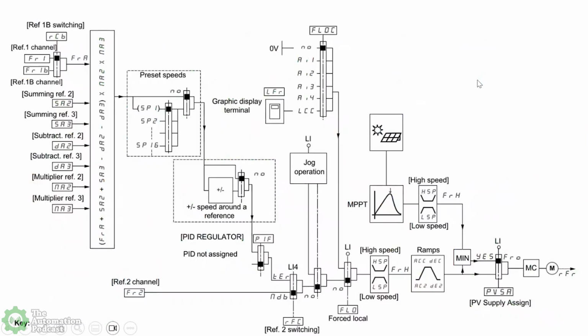Yes. There are obviously more things that we can do here. We can do some of the Boolean, the reference switching, and work on preset speeds. So there are a lot of very cool recommendations that we have in our installation manual on how to program through the logic, through the VFD parameters, and how to switch between references. If we're using a PID loop, all that will be available through the VFD. And obviously, anytime we go through the DC bus solar, activate the MPPT, and be able to switch into, for example, main and PID and other sources or programming within the VFD itself. So we can get extremely sophisticated, or we can keep the application as simple as possible. Back to your point, we can create a specific bill of materials for those that are interested in being part of the pre-launch and the development of this very cool technology.